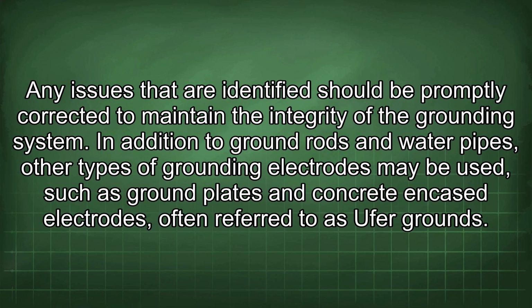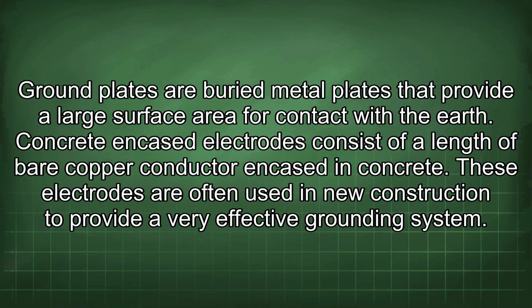In addition to ground rods and water pipes, other types of grounding electrodes may be used, such as ground plates and concrete-encased electrodes, often referred to as Ufer grounds. Ground plates are buried metal plates that provide a large surface area for contact with the earth. Concrete-encased electrodes consist of a length of bare copper conductor encased in concrete. These electrodes are often used in new construction to provide a very effective grounding system.